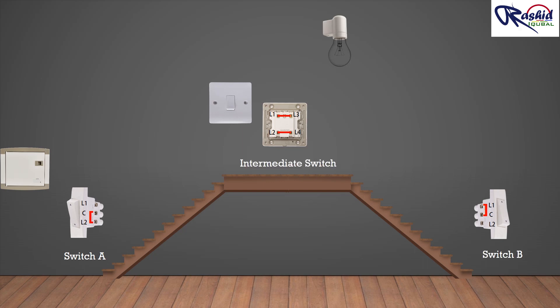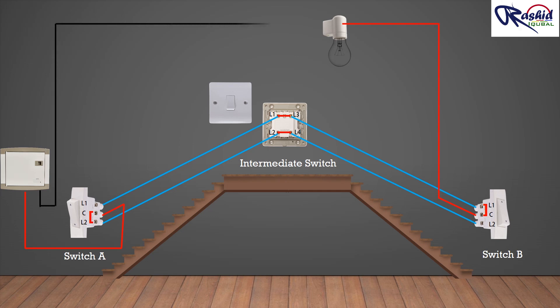L1 of switch A connects to L1 of the intermediate switch. Then L2 of switch A connects with L2 of the intermediate switch. L3 of the intermediate switch connects with L1 of switch B, and L4 of the intermediate switch connects with L2 of switch B. We take our live wire and feed it into the common of switch A, then run a wire from the common of switch B up to the light fixture. The neutral runs direct from the main power supply panel to the lighting fixture.